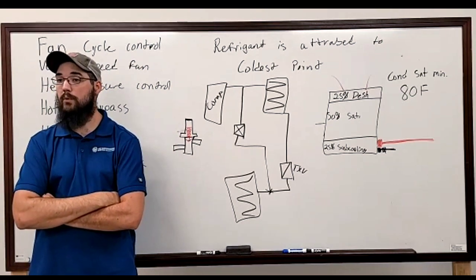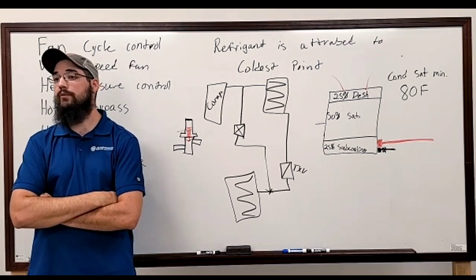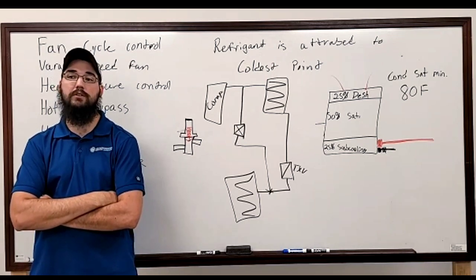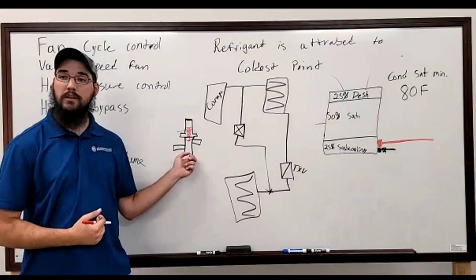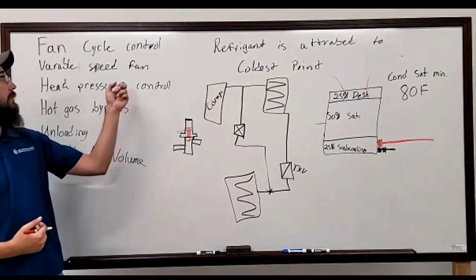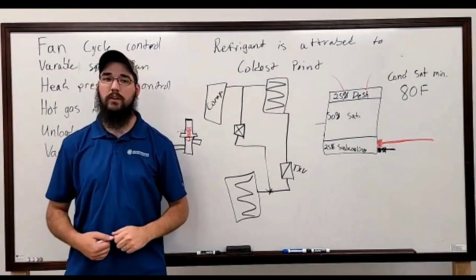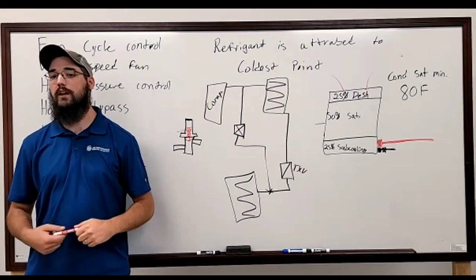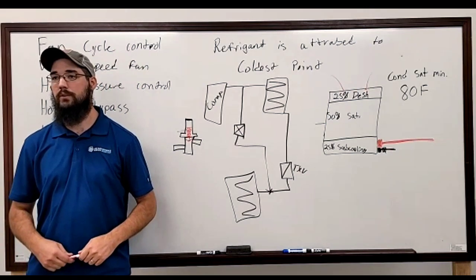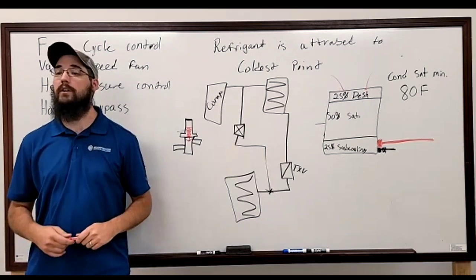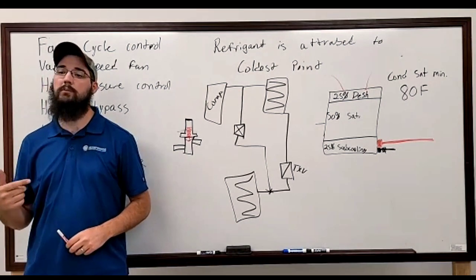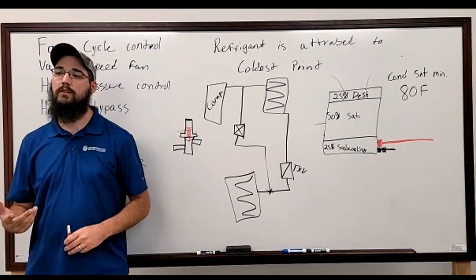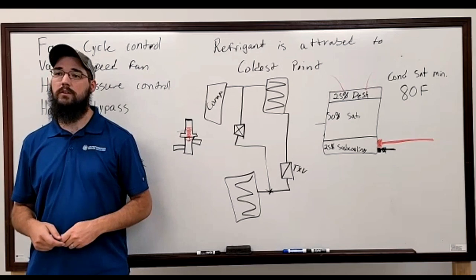And you can, up to a certain point, right? Because you can figure head pressure saturation ought to be pretty much degree for degree. There are a lot of things you can take into account. But when you get into a state where you're on bypass, whether it be HPR valves, or you've got fans cycling speeds, you're in no man's land. The system's not stable enough to know what to actually do. All you're really checking at that point is that you're not in a critical state, and you're making your best assessment that you're functioning within reason. That's really the most you can do at that point with any certainty.